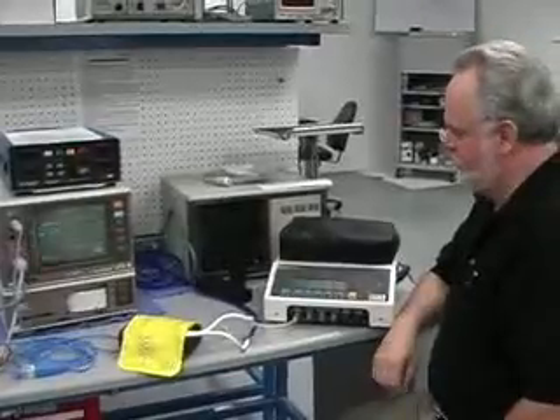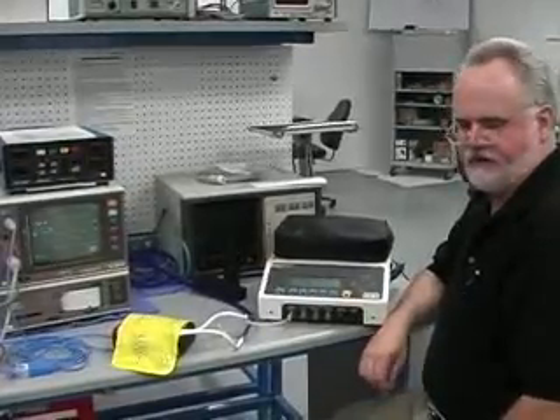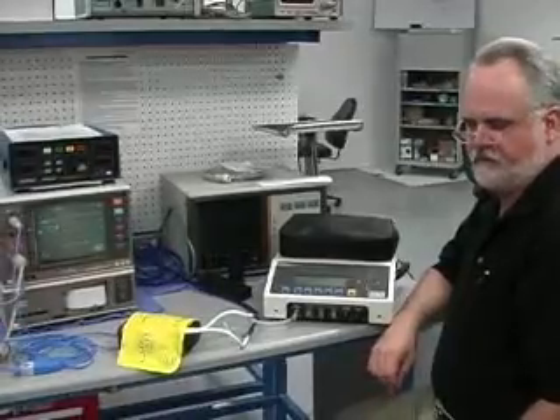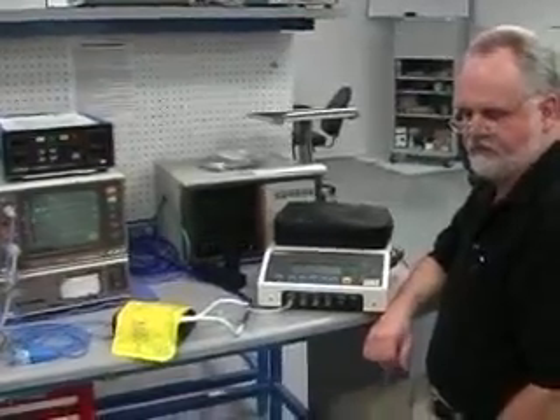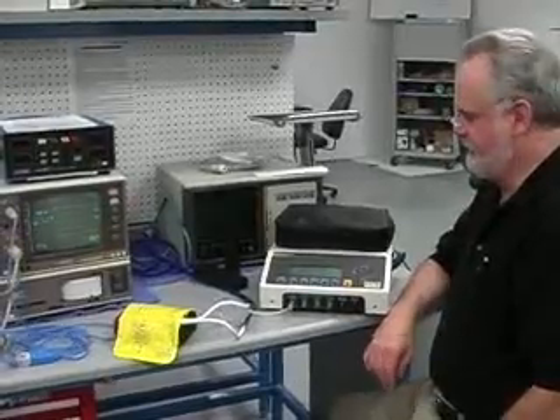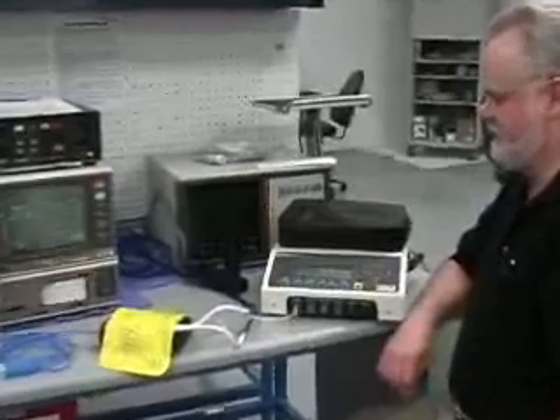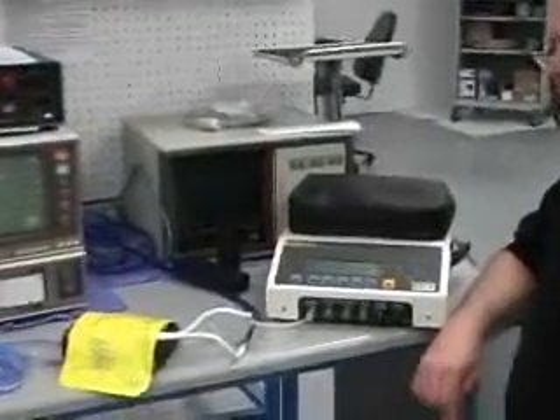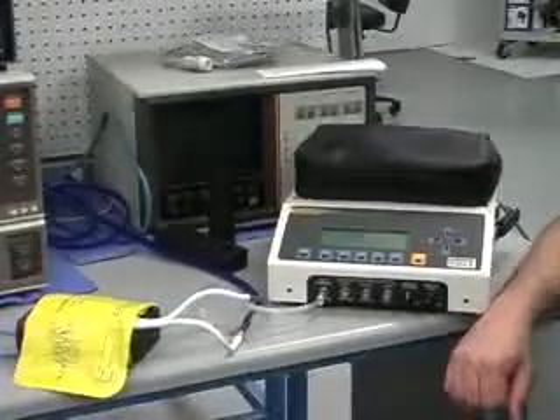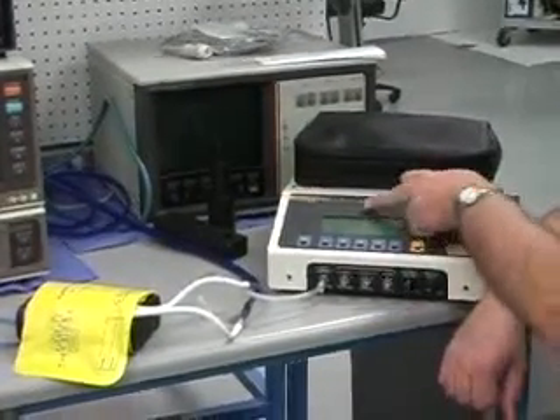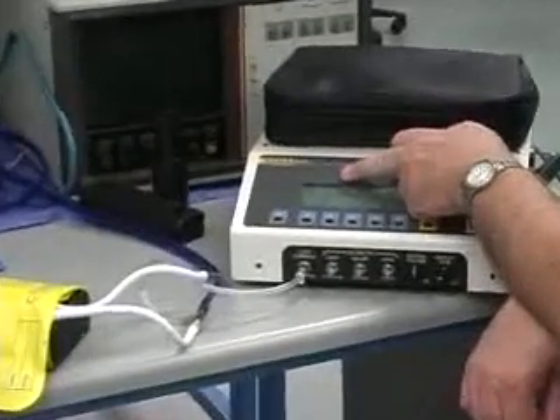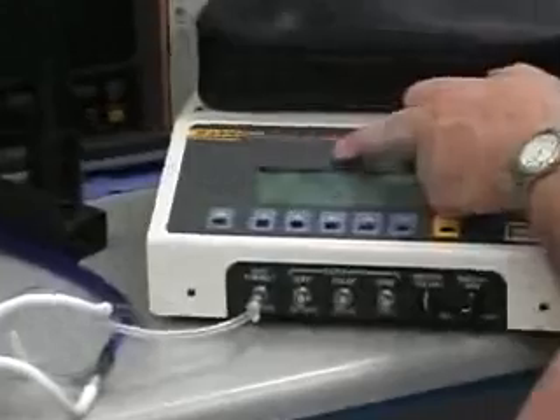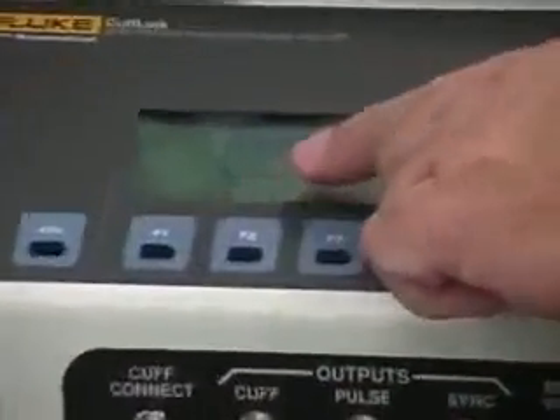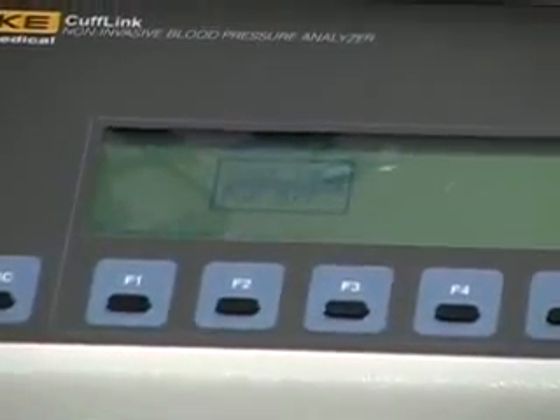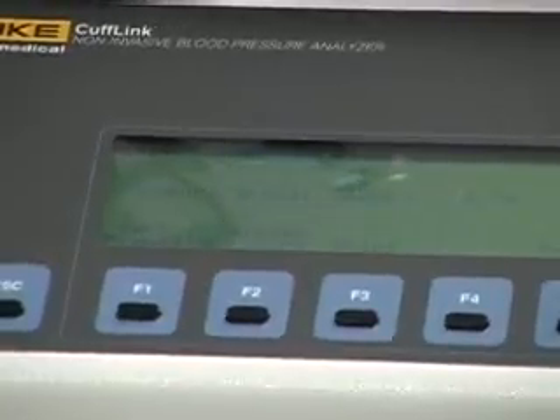Okay, we're just going to show doing some of the different performance tests on a non-invasive blood pressure unit using the Cufflink. These tests you're looking at are basically a manometer test, a leak test, and what is called a pop-off test. These tests are under the PRESS menu, or pressure menu, and they're listed as leak test, manometer, and pop-off. Using the cursor key controls, let's go to manometer and hit enter.